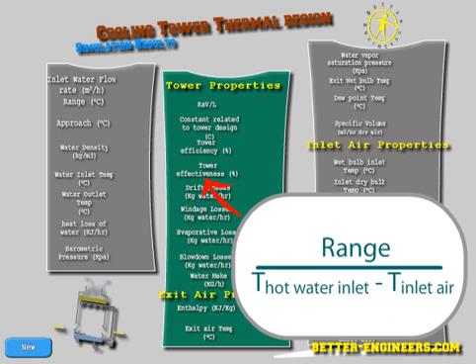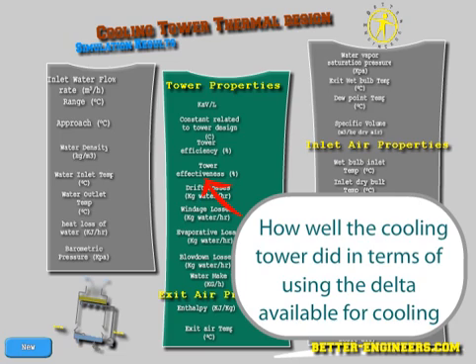Tower effectiveness, also in percentage, is the ratio of the range to the difference between the temperature of the hot water and the inlet air temperature. In other words, this tells us how well the cooling tower did in terms of using the delta available for cooling.